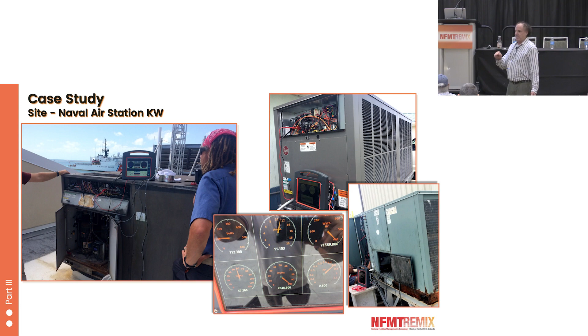And this is actually really key to make it work economically, is to only do the targeted service, because if you go in and do every possible thing to the unit and it only needs 2 out of those 5 or 10 things, then your technicians have spent a lot of time. And that's really the thing here, is to try to keep this down to about a 4-hour PM, which might be enough to replace a fan motor, adjust the refrigerant charge. They can't really go through a whole unit, which might take a whole day. They could do it, but I don't see where it would be worth their time to do that. So you really want to focus in on exactly what each unit needs.